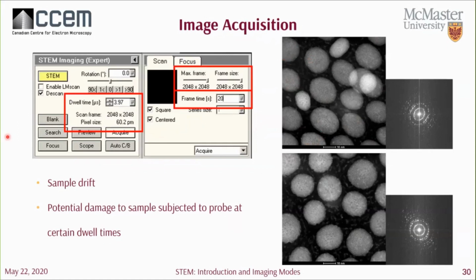This is just an example. If you're a little impatient, and I can be a little impatient sometimes, you don't let the sample settle on the microscope and you try to acquire an image. This is what you actually get. You can see that the stage or your sample was drifting in this direction, and you can see that in your FFT. Note that the stretching is not from astigmatism, but actually from sample drift.